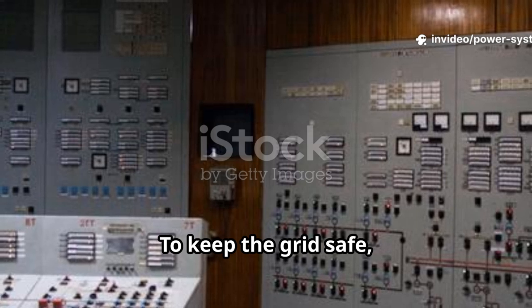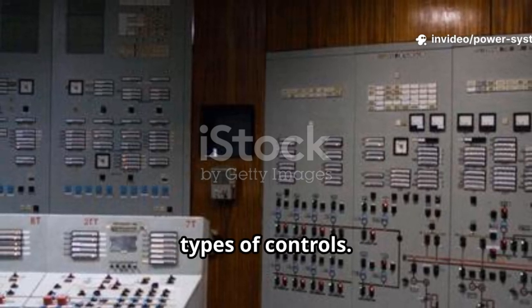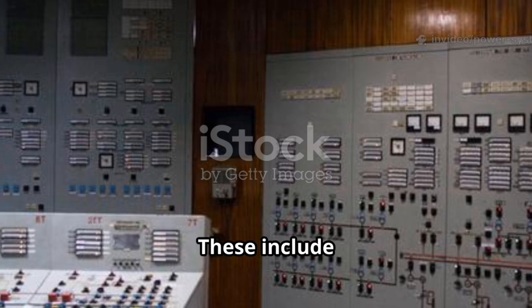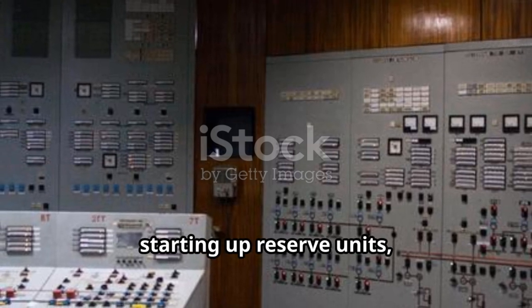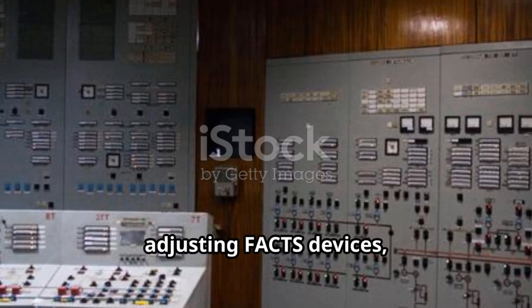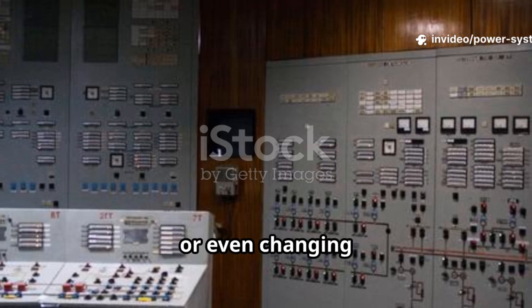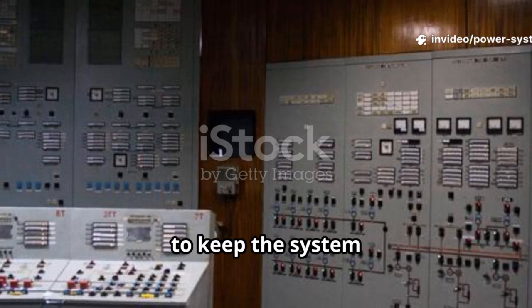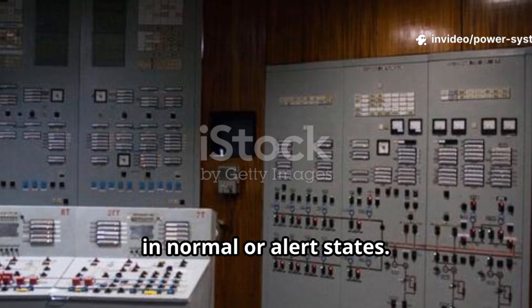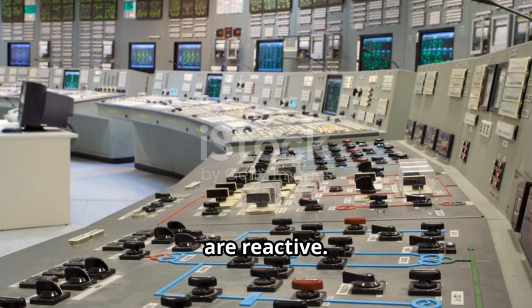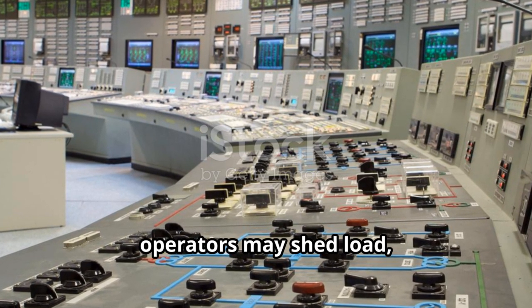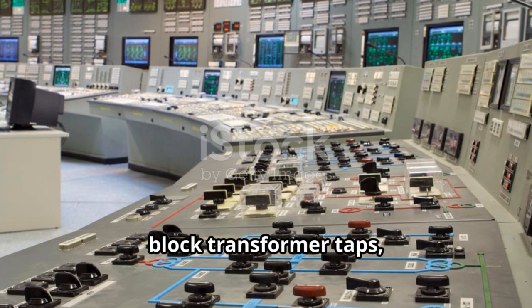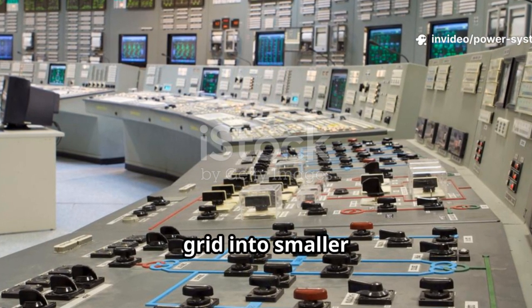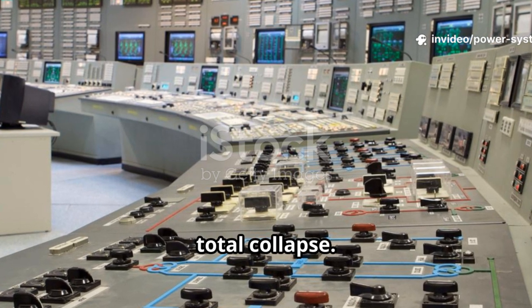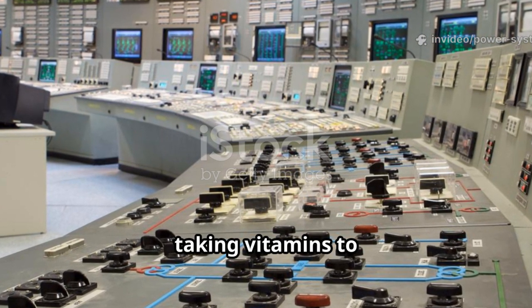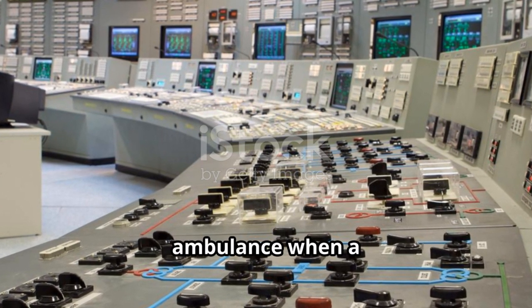To keep the grid safe, engineers use 2 types of controls. Preventive controls are proactive. These include rescheduling generation, starting up reserve units, switching shunt capacitors, adjusting FACTS devices, or even changing substation configurations, all to keep the system in normal or alert states. Emergency controls are reactive. When things go wrong, operators may shed load, trip generators, block transformer taps, or even split the grid into smaller islands to prevent total collapse. Think of it as the difference between taking vitamins to prevent illness versus calling an ambulance when a health crisis strikes.